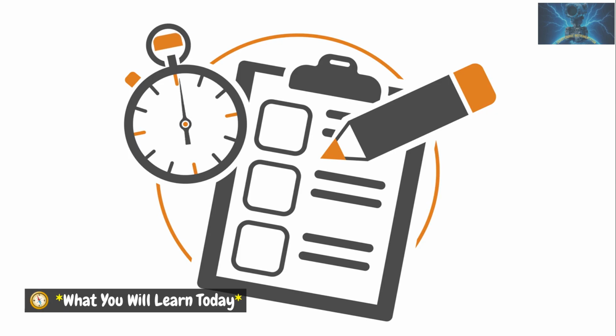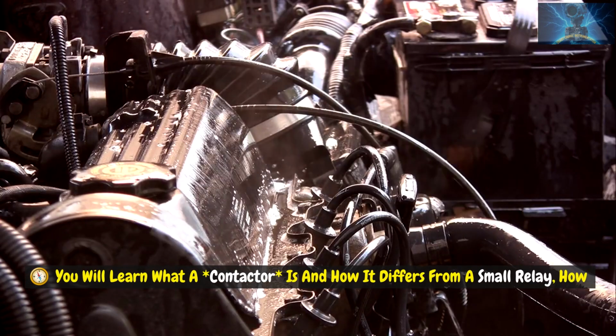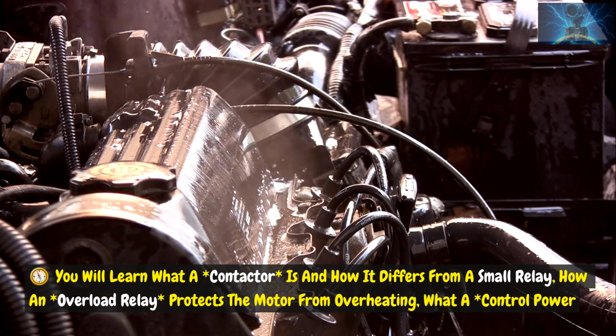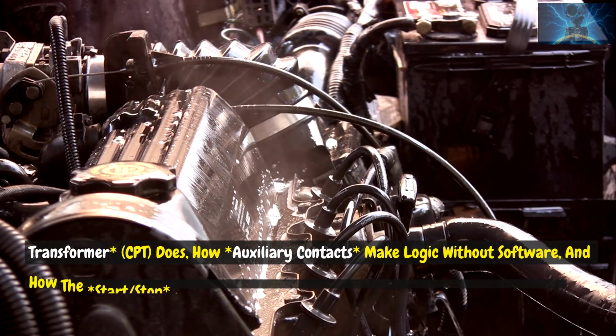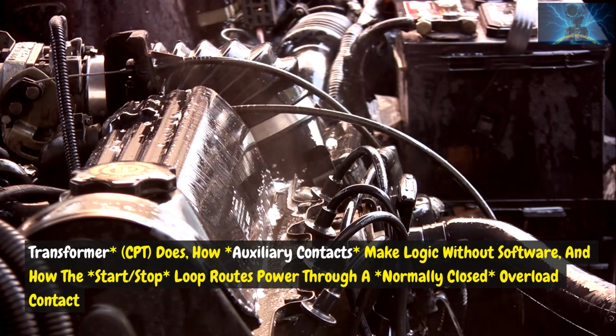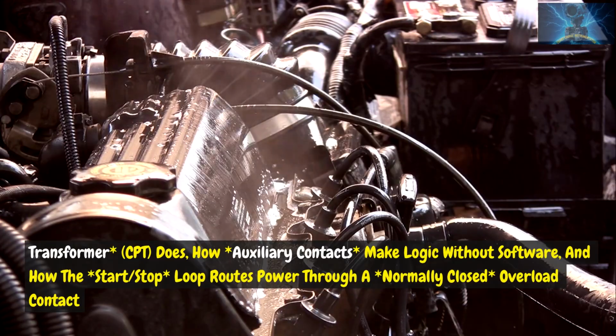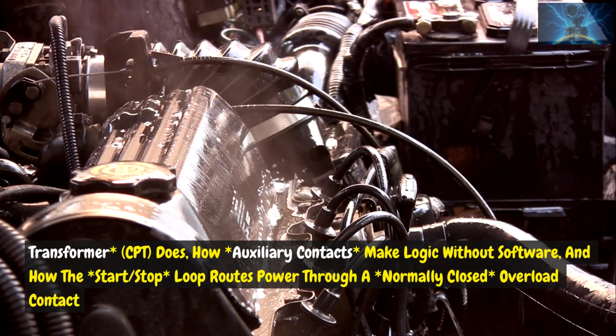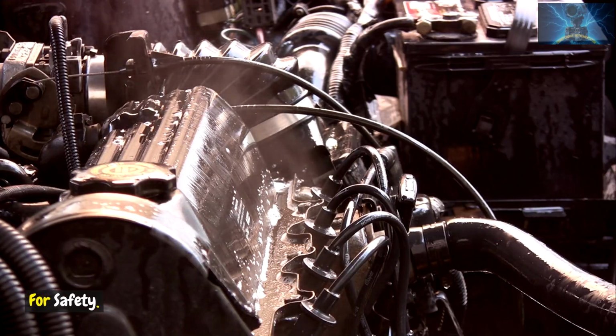What you will learn today. You will learn what a contactor is and how it differs from a small relay, how an overload relay protects the motor from overheating, what a control power transformer, CPT, does, how auxiliary contacts make logic without software, and how the start-stop loop routes power through a normally closed overload contact for safety.